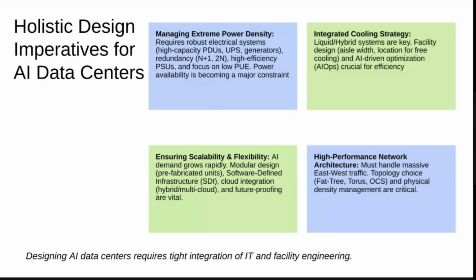This means robust electrical infrastructure, high capacity distribution units, reliable UPS systems, backup generation, designing for densities exceeding 40, even 100 kilowatts per rack. Energy efficiency, measured by power usage effectiveness or PUE, is paramount, and systems must handle the highly variable power demands of AI workloads. Power availability itself is becoming a major bottleneck in popular regions.